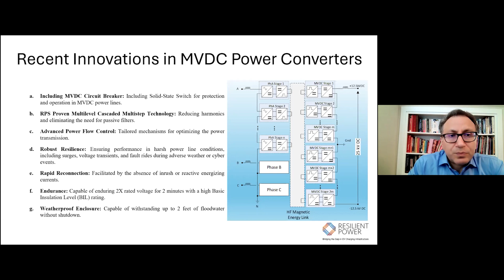And since they don't have any inrush current, they can reconnect very quickly. They are capable of 2 times the voltage for 2 minutes, and for our 15 kV class, we have 95 kV BIL, which is similar to the transformer standard.